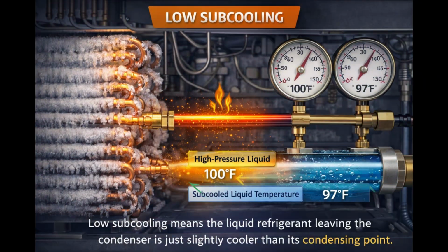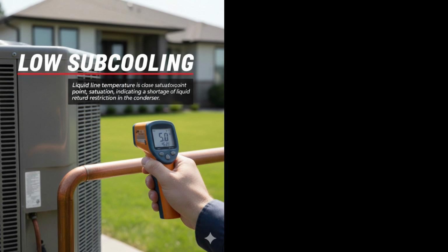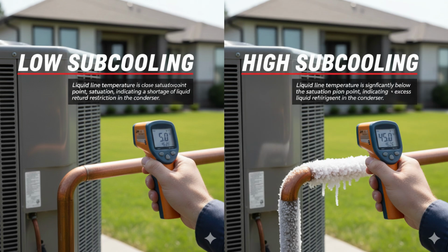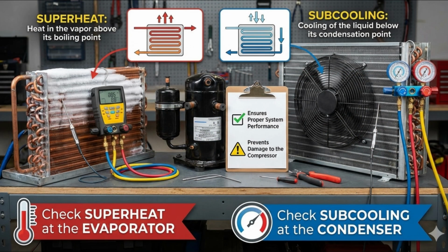Low subcooling means you don't have enough liquid refrigerant, which points to a possible undercharge. High subcooling usually means refrigerant is backing up in the condenser, and this could be indicating a possible overcharge or a restriction.